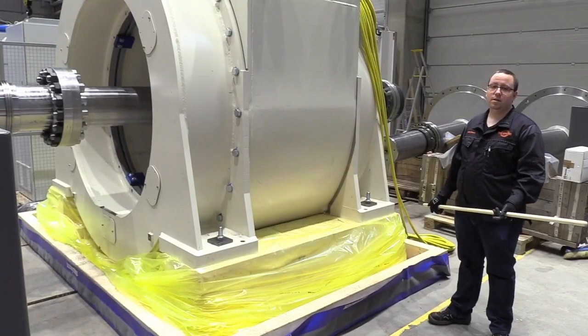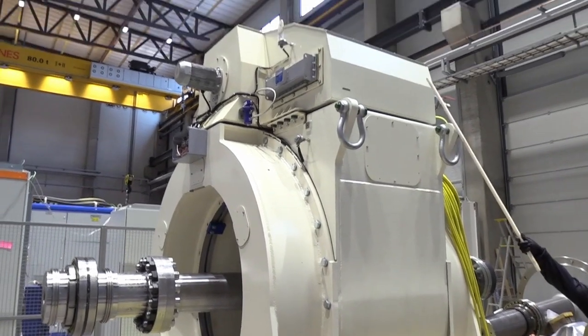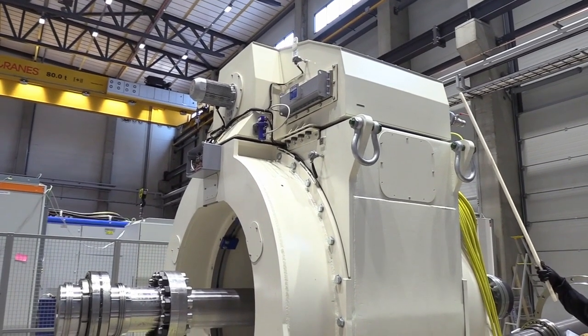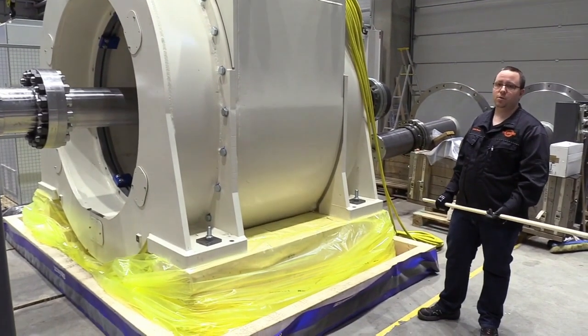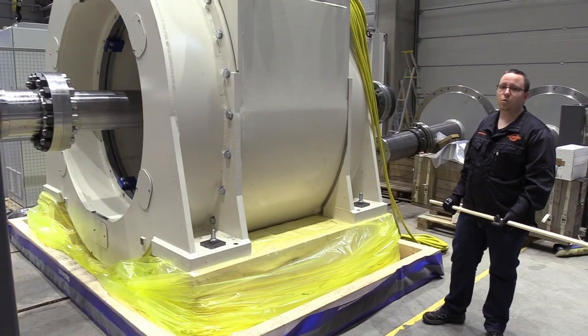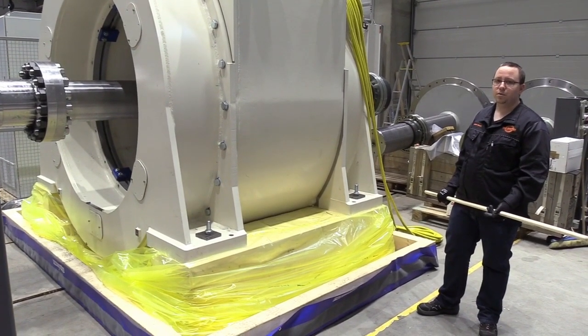The machine has emergency air flaps located here, another one on top of the cooling unit, and then two more on the opposite side. These emergency air flaps should only be opened in case of cooling line liquid failure. Please refer to the user manual for more information.